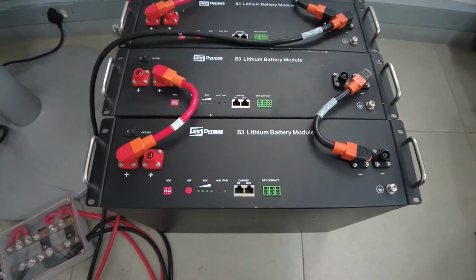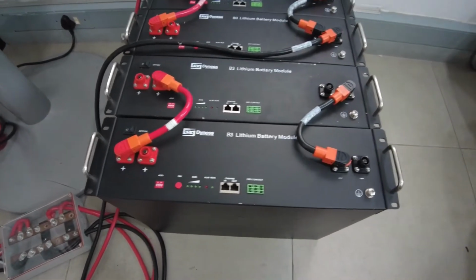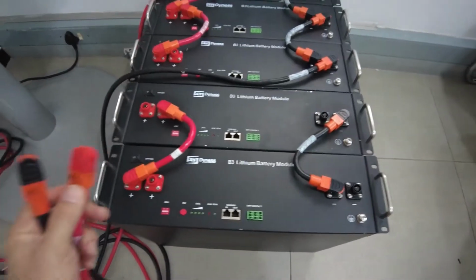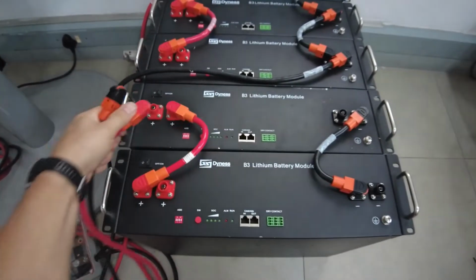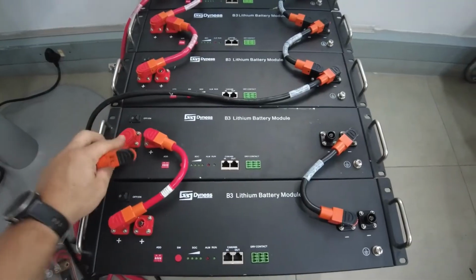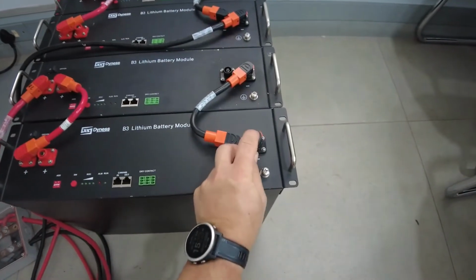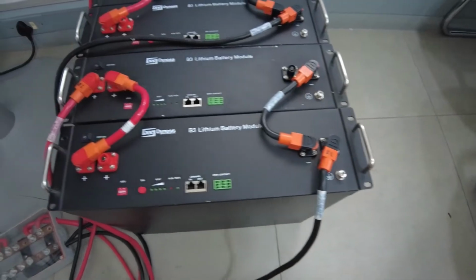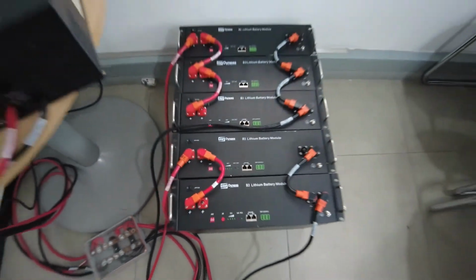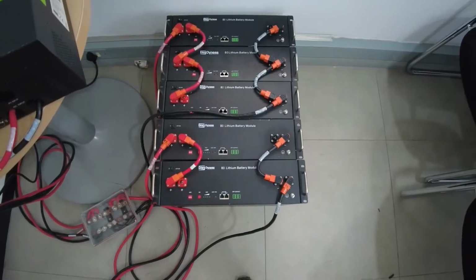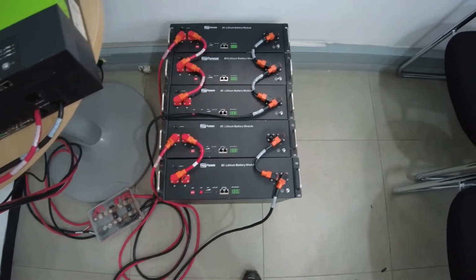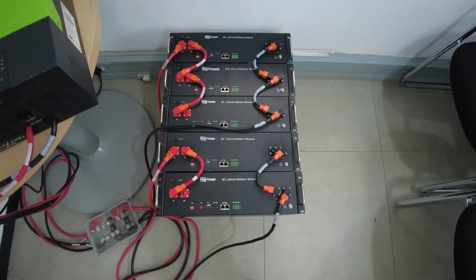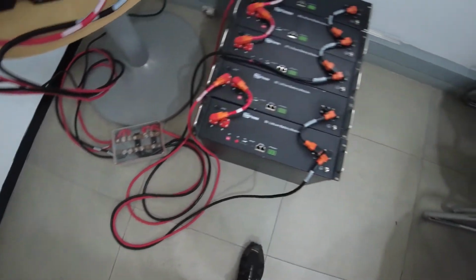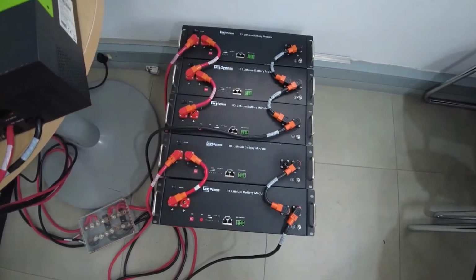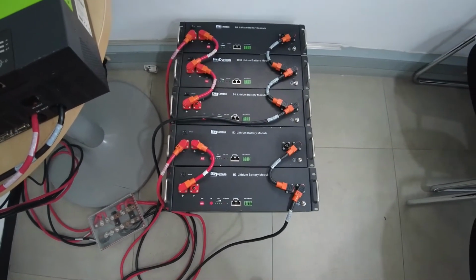Now we need to connect the second pair of cables, again from the same combiner box. You have your positive to the top going across the battery bank, and you will connect your last remaining battery. So technically all of these batteries are now parallel connected from the same combiner box. So even though you do have two different banks of batteries, they will evenly charge.